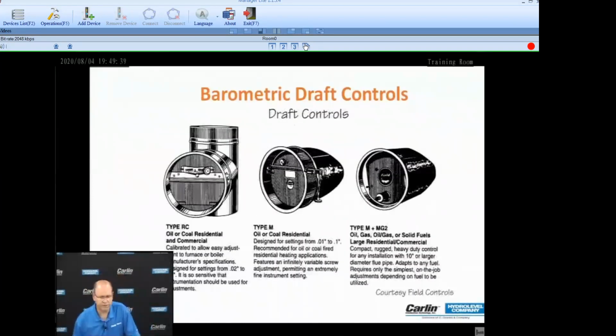Barometric draft control. Well, this is probably the most ignored component on a system. I see them installed wrong all the time. You know, the most common mistake is the screw just drives right through, prevents the damper from opening fully or even opening at all. Sometimes it's done on purpose. Sometimes they'll put a screw through it so it doesn't open, so it doesn't blow back whenever the appliance starts.